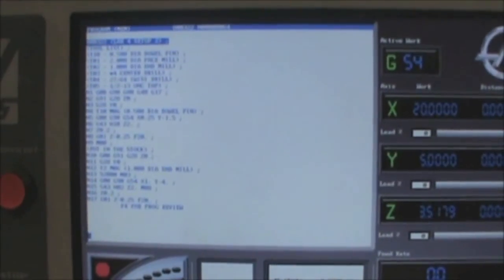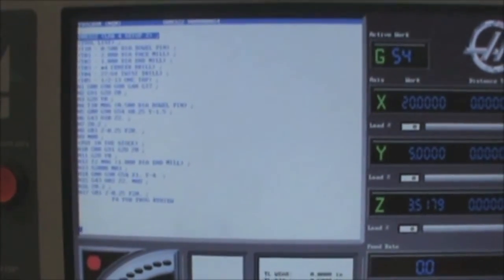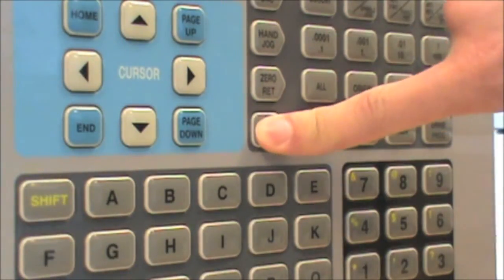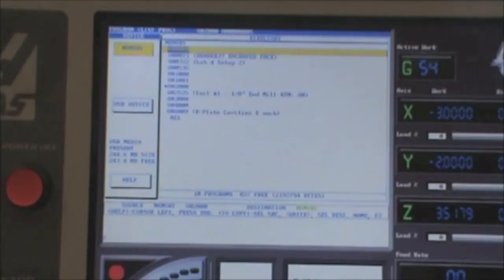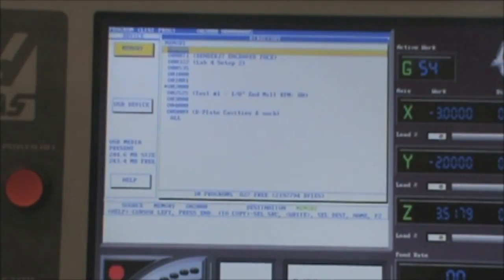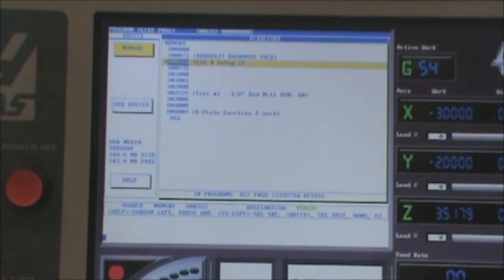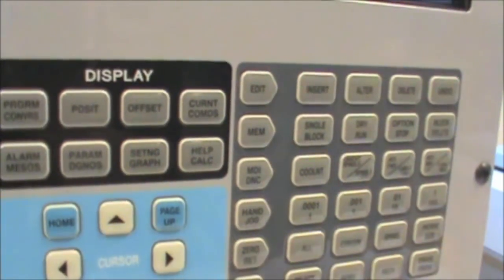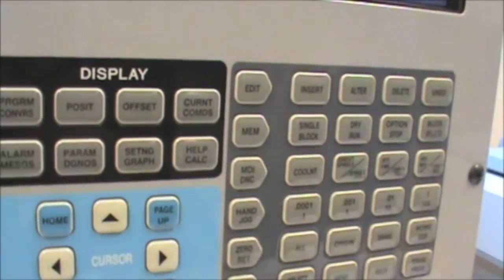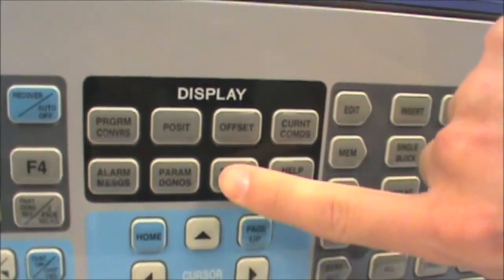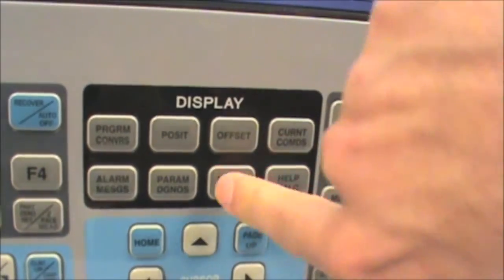Now that the program is loaded, it can be simulated on the controller. First, go into the list program mode to ensure your program is selected. If the asterisk is not next to the program you want to simulate, press the right arrow to activate the right panel, and then use the up and down buttons to scroll through the list of programs. Once the desired program is highlighted, press the select program button. Once your program is selected, enter memory mode by pressing the memory mode button. To change the graphic display, press the setting graph button twice.